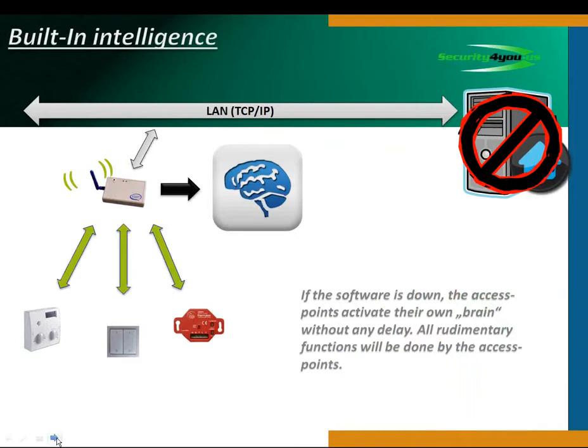What's really neat about this system is you can go with or without an on-site management software tool. This system will actually work in what we call dumb mode — it does rudimentary activities like unoccupied sensing. When you take the key out, everything goes into unoccupied mode with no server driving it. The only time we get into servers is when we get into monitoring energy costs. This system will go through and per device — or globally — show you energy costs per unit, per month, or however you want to import it.